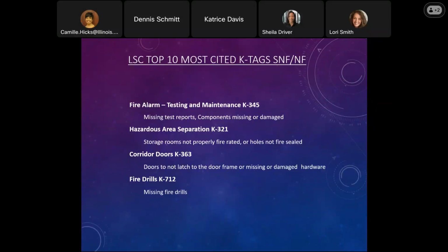Hazardous area separations, that's more for storage rooms. Some facilities convert a resident room into a storage room because they're no longer using it. Well, it needs to be properly fire rated. The door doesn't have a closer. Is it a solid core wood door? There are many issues where they've converted rooms into storage rooms and they don't comply with the requirements of K321.